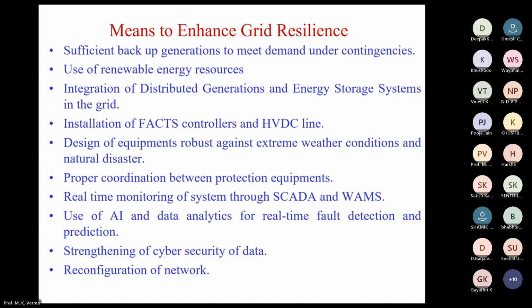An HVDC line has an infinite stability limit, so it is more stable compared to an AC system. We also have controls on both-side converters through which you can have quick recovery of the system. We can design the system to be robust against extreme weather conditions. Suppose you are designing conductors, and we are putting up lines, poles, and towers, they should be robust and able to bear extreme weather conditions and natural disasters.